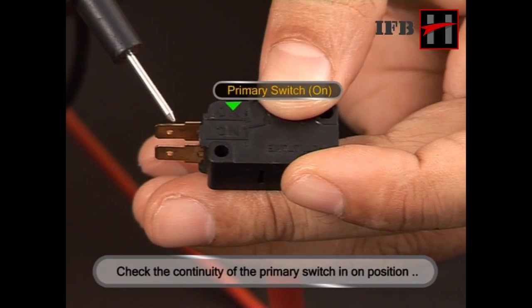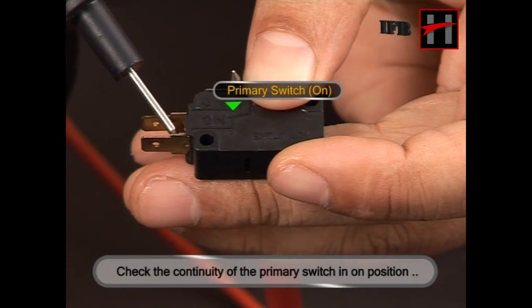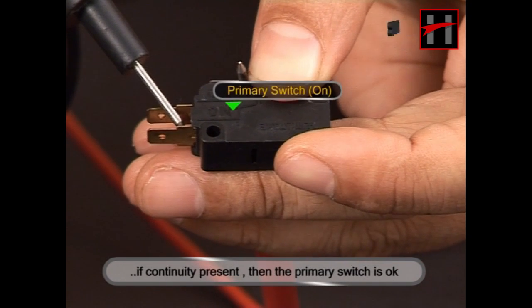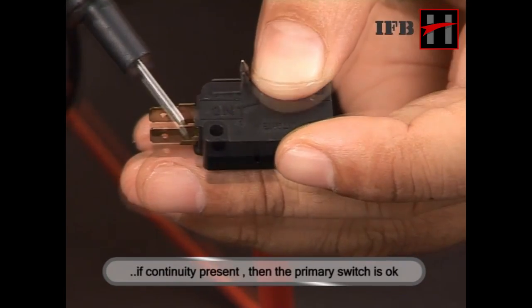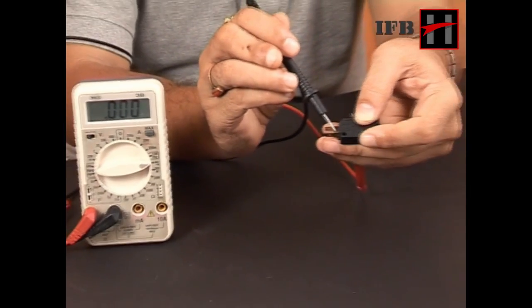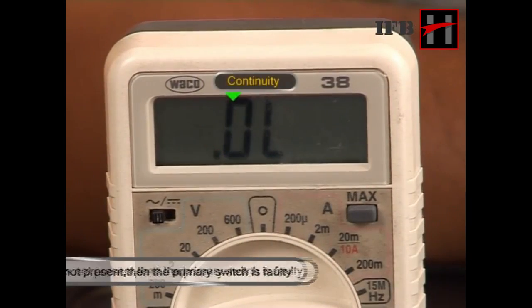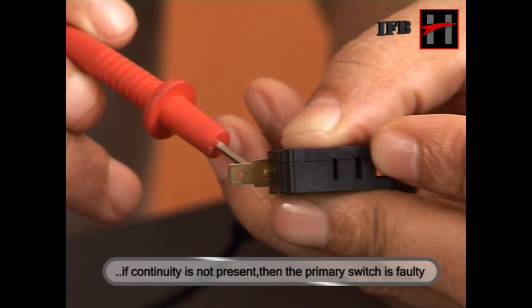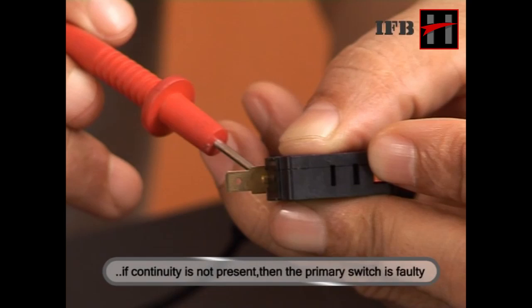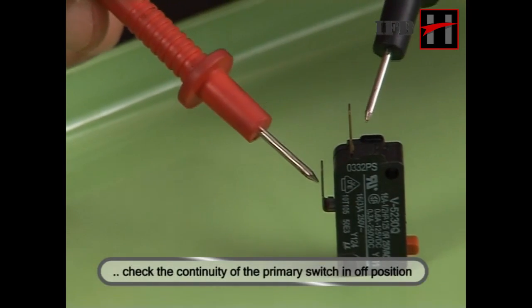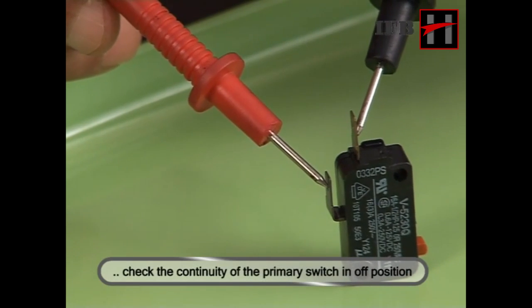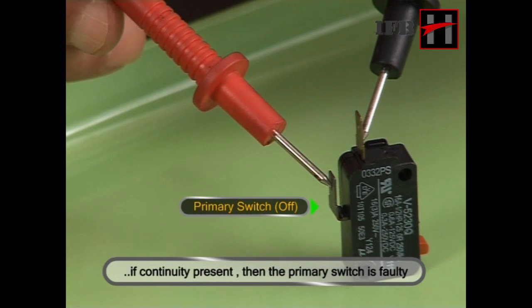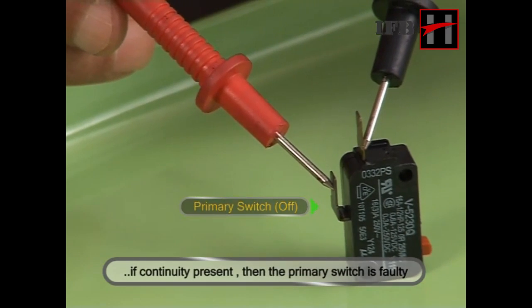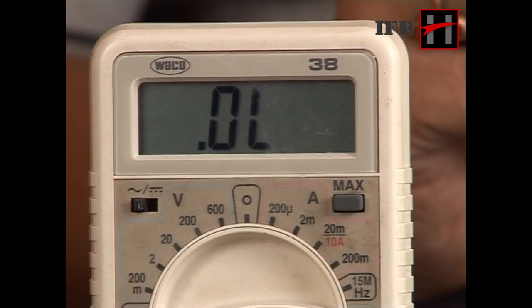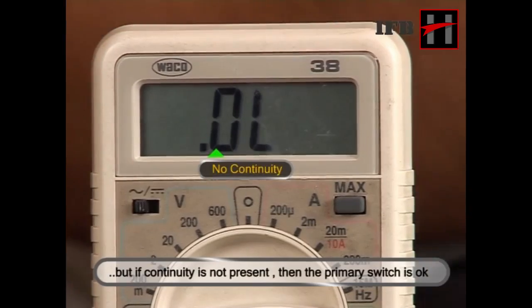Check the continuity of the primary switch in on position. If continuity is present, then the primary switch is OK. If continuity is not present, then the primary switch is faulty. Similarly, check continuity of primary switch in off position. If continuity is present, then the primary switch is faulty. But if continuity is not present in this situation, then primary switch is OK.